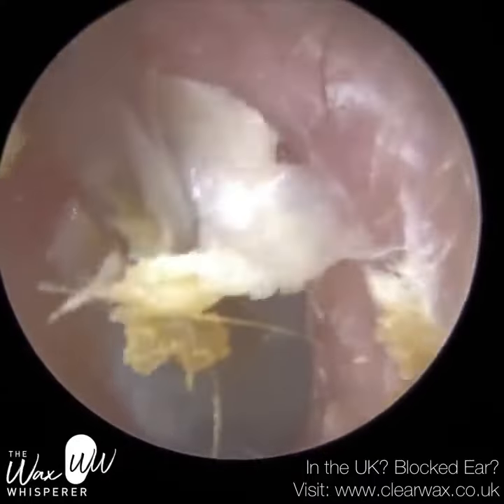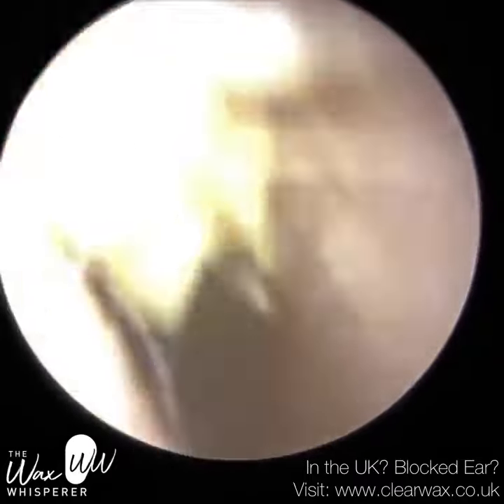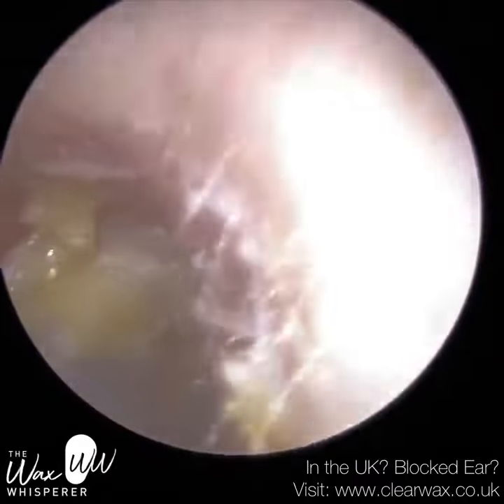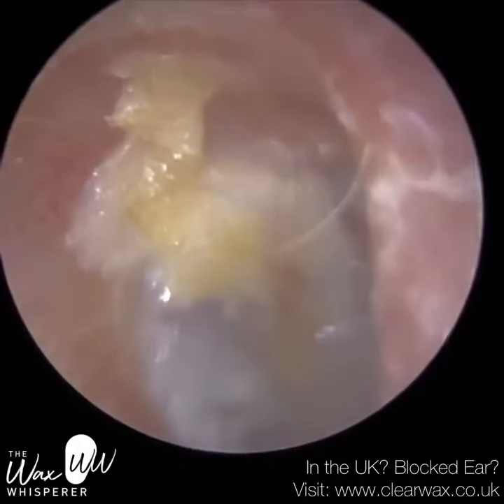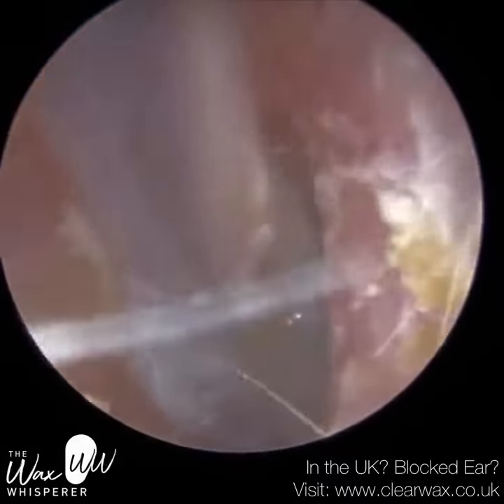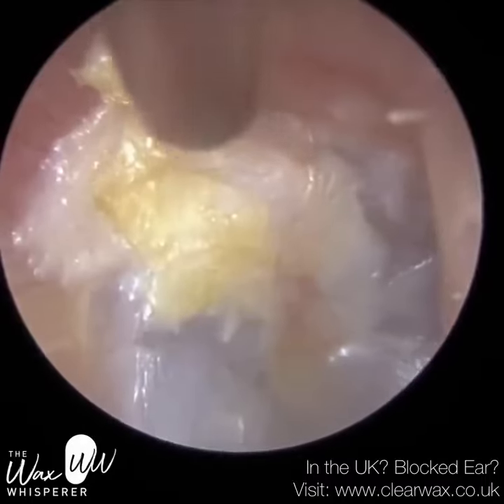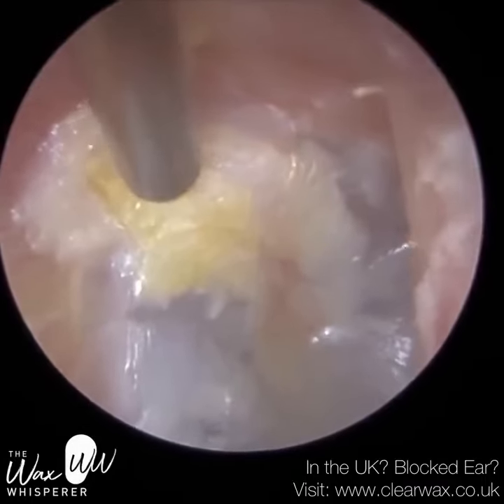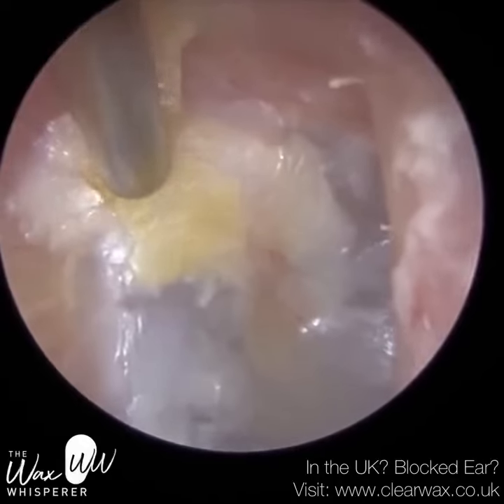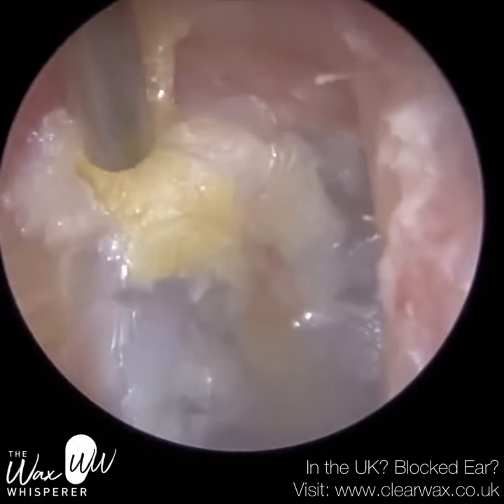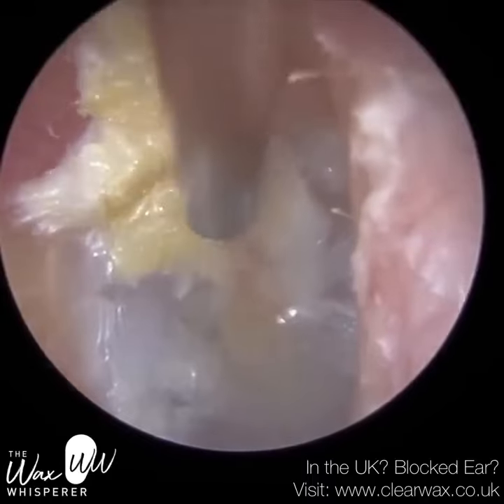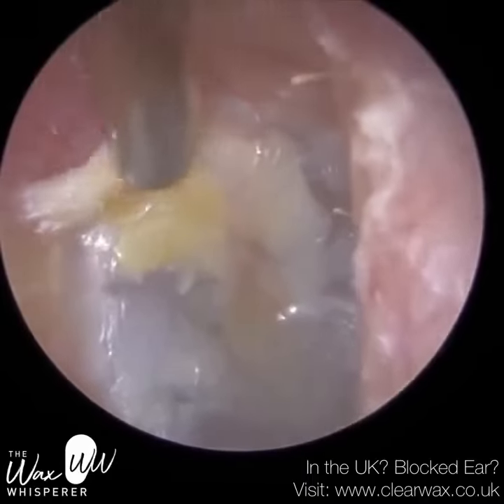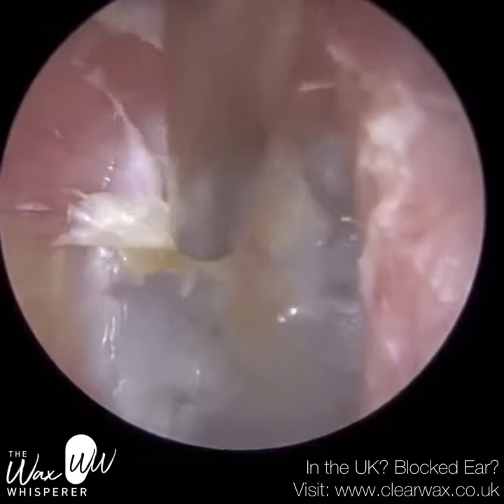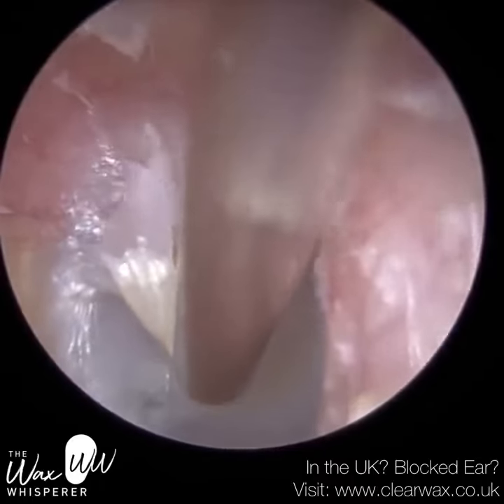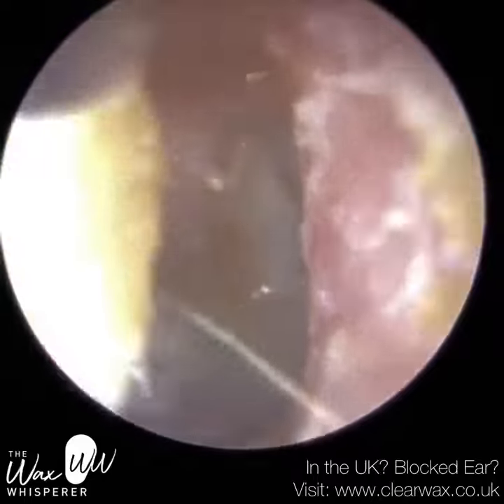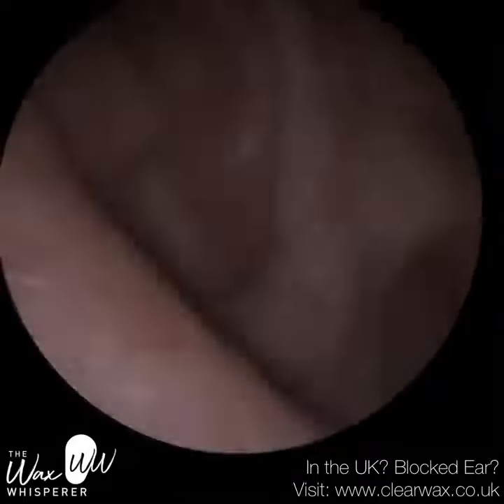The internal diameter of the fine end suction probe is about 1 millimeter. In comparison, the standard Zollner suction probe that we typically use has an internal diameter of around 1.7, so the fine end is almost half the diameter of a standard Zollner suction probe. When we're working on the eardrum as we are here, the fine end comes into its own. Because it's a narrower tip, it provides more precision and accuracy, and if you do come in contact with the eardrum, it's less likely to cause any physical trauma.